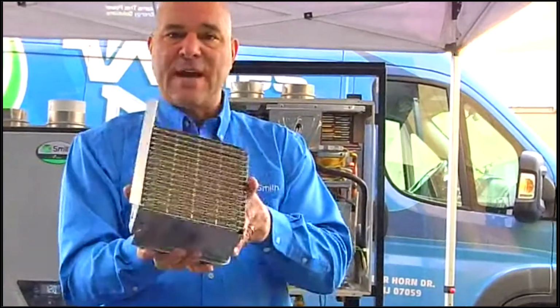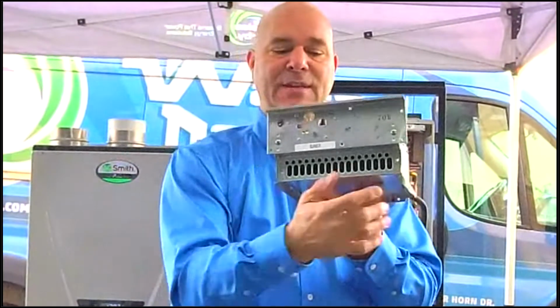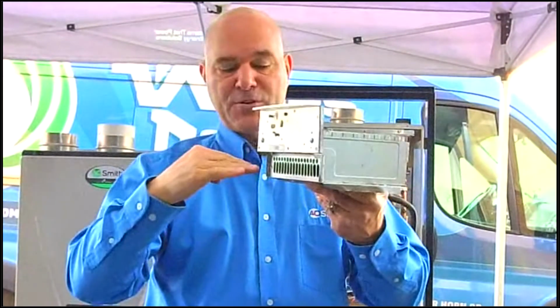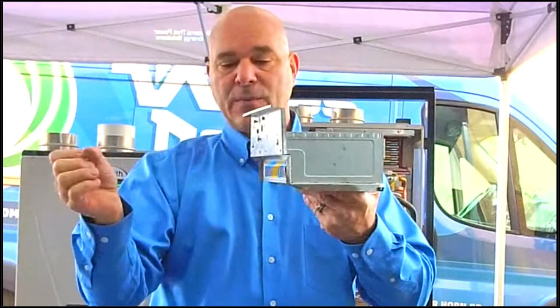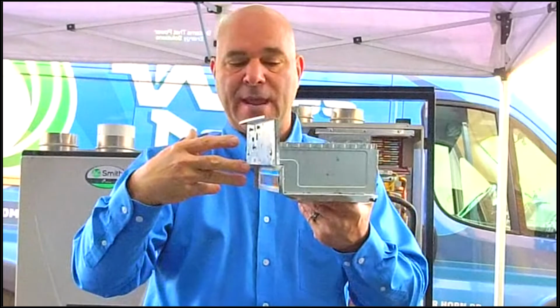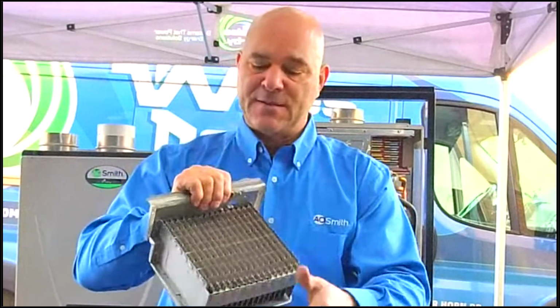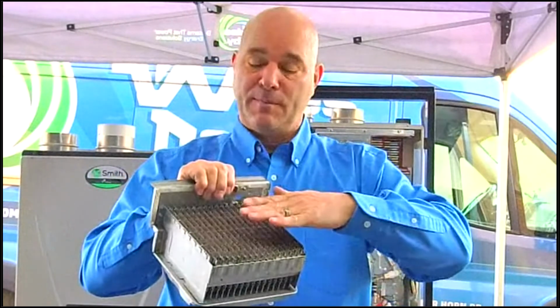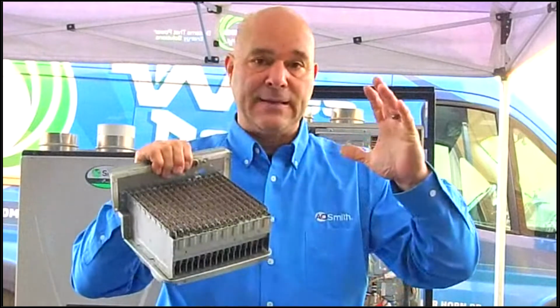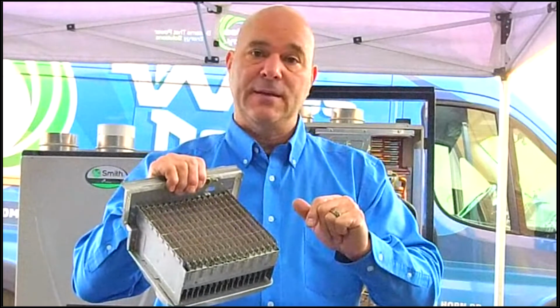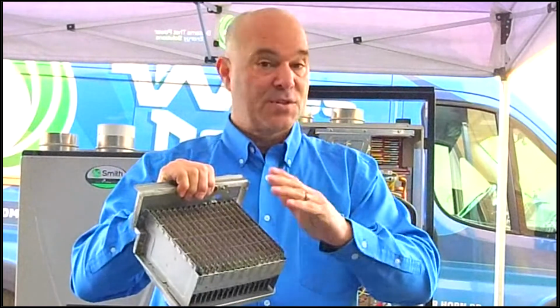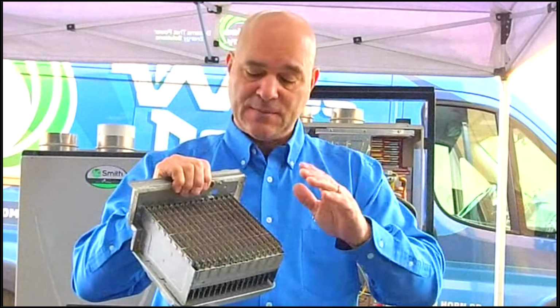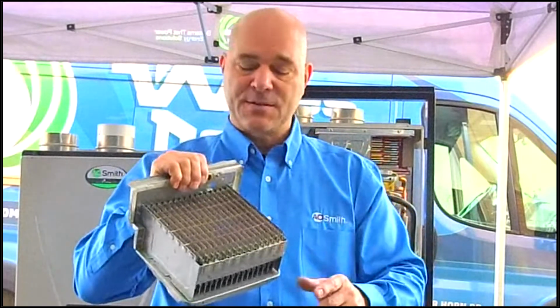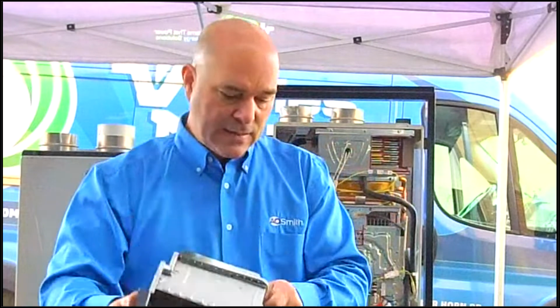So this is not a pre-mix. We actually inject. It looks like a bunch of orifices sitting right here. We inject the gas in, we pull the air in with it, and it mixes on top of the burner, and you'll have normal burner flames off of here. It's not like the high intensity glow like you'll see in a high efficiency boiler. We're still 95% efficient, but you'll have a standard style burn going on here.